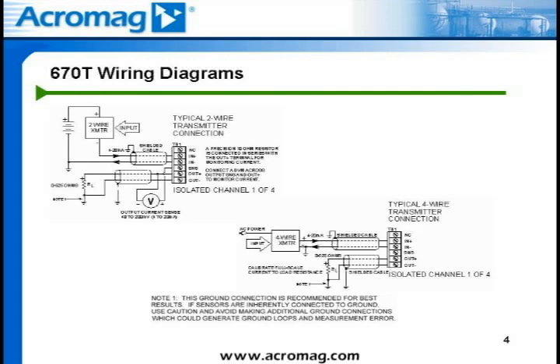The 670T also has an SNS or sense terminal. This is not a terminal to tie in the shield from a twisted shielded pair cable. A voltage meter can be connected to this sense terminal and the output-plus terminal of the 670T module. Internal to the 670T isolator is a 10-ohm precision resistor that will convert the 4 to 20 milliamp DC output signal to a 40 to 200 millivolt signal. By placing the voltage meter on these two terminals, the 40 to 200 millivolt signal — identical to the 4 to 20 milliamp DC signal — can be monitored without disturbing the output loop.